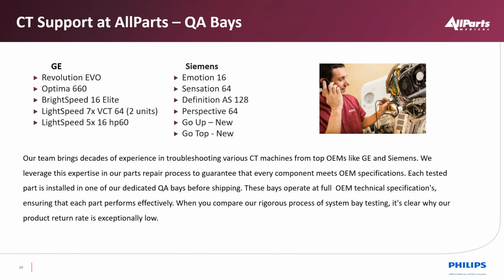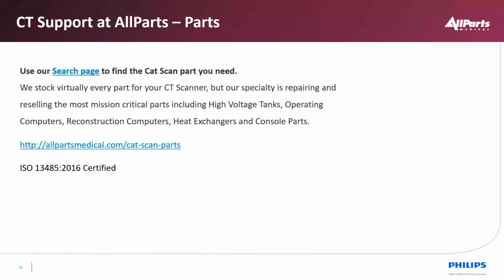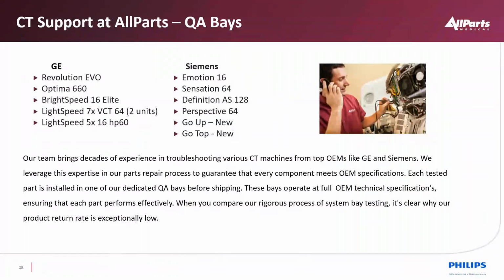When we talk about the repair process, a lot of vendors out there will repair a high voltage tank or something on a bench, but they never actually put it on a scanner to validate that it doesn't have air bubbles in it or something like that. So with regards to here, we actually take the parts that are repaired and put them back on the scanner and validate that we get a good quality image. And so the part has been tested on a rotating frame to validate that we have good image quality before that part's taken off and put on the shelf for sale or exchange.